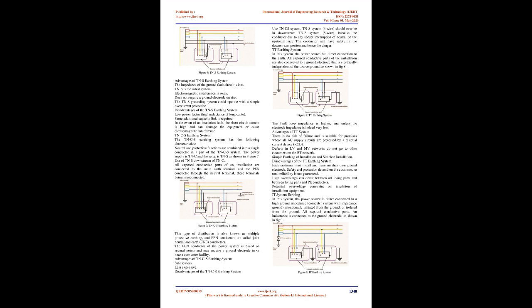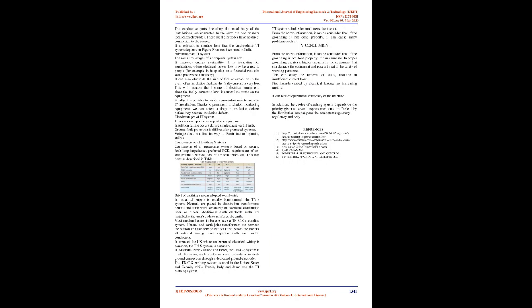IT system earthing: in the system, the power source is either connected to a high ground impedance, intentionally grounded through an impedance, or isolated from the ground. All exposed conductive parts are connected to the ground electrode, as shown in Fig 9. The conductive parts, including the metal body of the installations, are connected to the earth via one or more local earth electrodes. These local electrodes have no direct connection to the source.